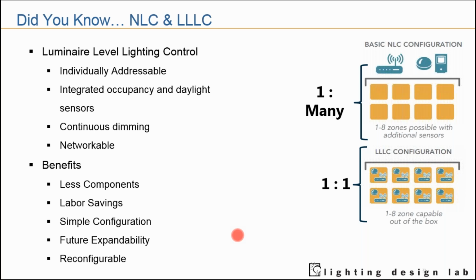They have to be individually addressable, so each fixture can respond on its own. Each need to have a daylight and occupancy sensors. Each fixture needs to be able to be dimmed continuously, and they all have to be networkable. And when I say networkable, I don't necessarily mean, hey, each fixture by default is going to get an IP address. No, by networkable, it just means that it can be communicated to very easily. It can be easily reconfigured, whether it be from a commissioning remote, a phone app, a computer program, just a way to communicate to this fixture to change its settings in an easy way without having to go in the ceilings.